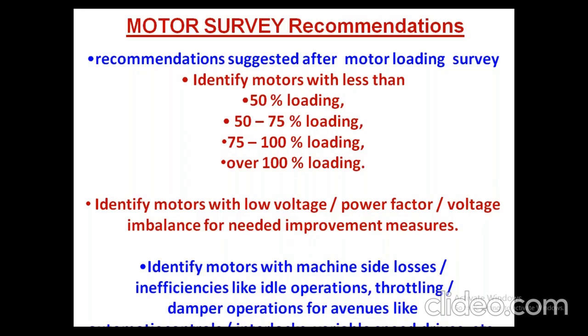And from the motor end, we have to see that the motor is getting the correct voltage, not low voltage, the correct power factor, and that voltage imbalance is not there. Once voltage imbalance is there in the motor, automatically derating of the motor is there up to 25%. With 5% voltage imbalance at the motor end, the motor straight away gets derated by 25%. I think our J.S. Srinivasan would have discussed more about the motors.